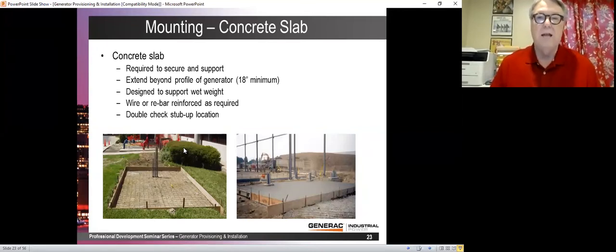The concrete slab, obviously, we want to make sure that the conduits come up in the right place. Pretty hard to move them after the generator is poured. And typically, we like to extend them 18 inches beyond the profile of the generator. That is not required. And maybe even most generators have less than that.